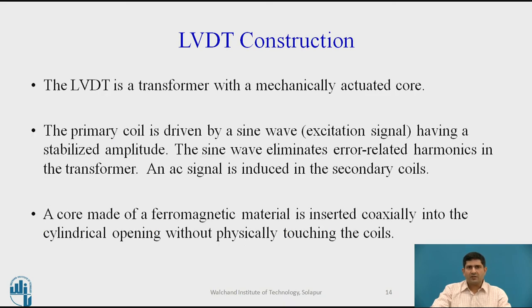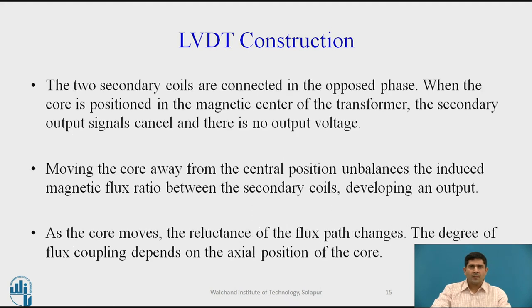Basically, the LVDT is a transformer with a mechanically actuated core. The primary coil is driven by a sine wave excitation signal of stabilized amplitude, which eliminates errors related to harmonics, and an AC signal is induced in the secondary coils. The core is typically a ferromagnetic material inserted coaxially into the cylindrical opening without physically touching the coils — so this is non-contact with no friction involved, which is one reason it gives very accurate measurements. Moving the core away from the central position unbalances the induced magnetic flux between the secondary coils and develops an output. As the core moves, the reluctance of the flux path changes, and the degree of flux coupling depends upon the axial position of the core, which is the displacement being measured.